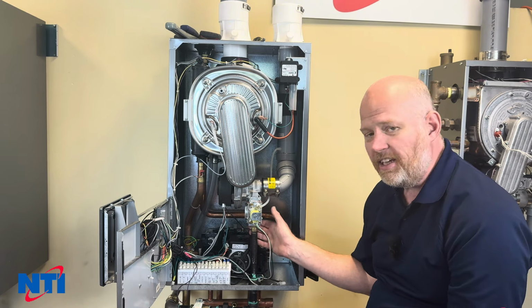We're going to take the 2 screws out. If you have an application like mine, with a flexible connector on the gas line, you can just move this out of your way to get that little bit of extra play. If yours is rigidly piped, you'll want to break the union and remove the gas nipple from the bottom of the valve. And again, if you have tools like a small Allen key that'll get in the back, you can do this without doing it this way. It just makes it a bit easier potentially. So now that I've got that moved, let's pull the line off.